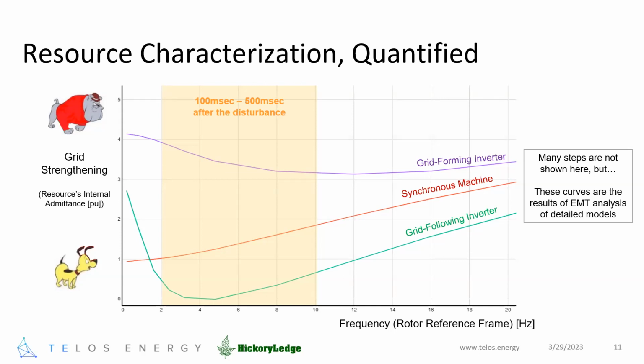Similarly with grid forming inverters, shown in purple at the top, there's a couple things to notice. One, grid forming inverters provide more grid strengthening than grid following inverters—expected. Also, they do it more than the synchronous machine example based on real synchronous machine parameters here. That's noteworthy. And two, they do it for the whole range of interest, up to about 20 hertz, so they're doing a good job regulating voltage for what I'd consider the critical bands for stability.